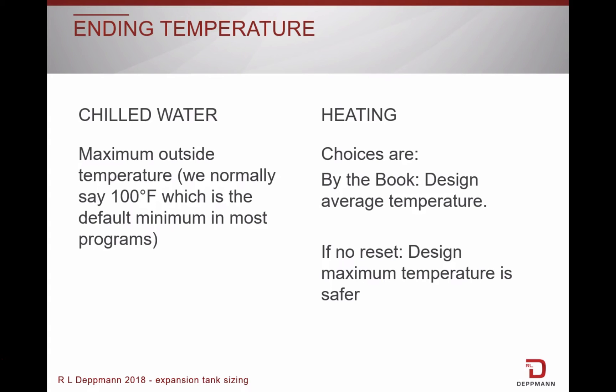There are two ending temperature choices for a heating system. Choice one, by the book: the design average temperature. Or you could go with choice two, if no reset: the design maximum temperature. It is safer.